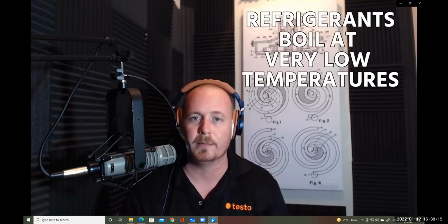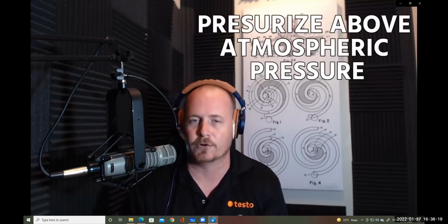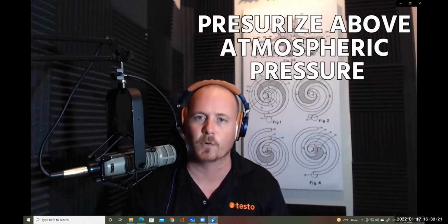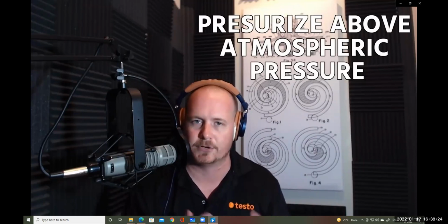And the only reason we imagine that is because the only thing we observe boiling in our day-to-day lives is water. And water does boil at a high temperature compared to our skin at atmospheric pressure. 212 degrees Fahrenheit or 100 degrees Celsius is what water boils at atmospheric pressure. Whereas most of the refrigerants we work with boil at very low temperatures at atmospheric pressure. In fact, we have to pressurize them above atmospheric pressure in order to manipulate them to boil at the temperatures that we want.